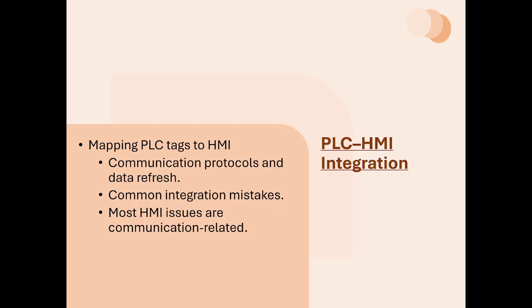So remember I described the PLC as meaning the programmable logic controller, and it contains the actual control logic that controls the process. While the HMI, the human machine interface, does not create information on its own. It only displays what it receives from the PLC. So what does integration mean? Integration means correctly linking PLC variables, which are called tags, to the objects you see on the HMI screens. Now, when tags are wrong, outdated, or poorly mapped, operators are misled. So PLC HMI integration is about trust, and operators must trust what they see.